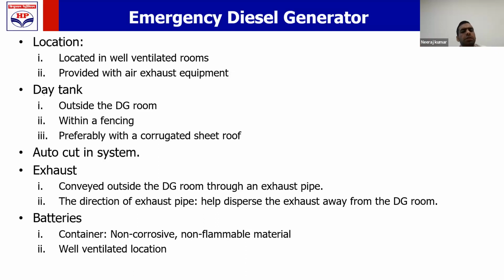Batteries of DG. Should they be kept in open, closed, where? The batteries of DG shall be kept in a non-corrosive, non-flammable container. It should not be flammable, it should not be corrosive. MS का मेटल का कंटेनर लगा दिया, नहीं तो प्लास्टिक का कंटेनर लगा दिया, नहीं चलेगा. DG battery container shall be non-corrosive, non-flammable material.